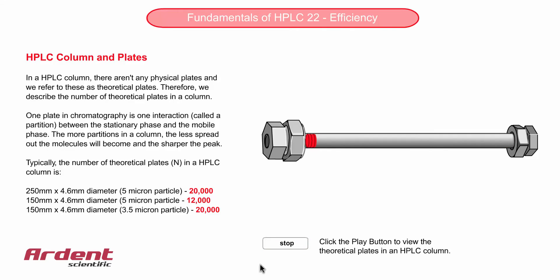The size of the particle of the stationary phase is typically about 5 microns, and a typical length of the HPLC column is about 250mm long. If the length of the column is shortened, then the plate count is shortened proportionately.